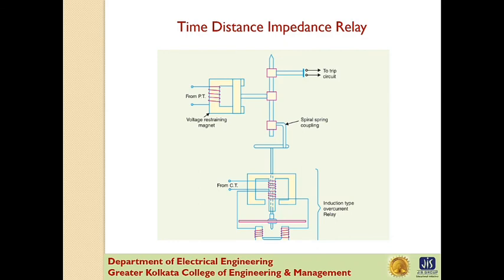The bridge is normally held in the open position by an armature held against the pole face of an electromagnet excited by the voltage of the circuit to be protected. Now, under normal operating condition, the pull of the armature is more than that of the induction element, and hence the trip circuit contacts remain open.